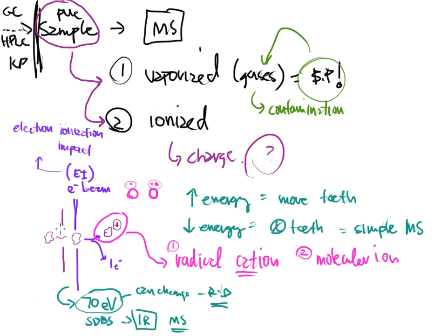So the sample comes into the MS chamber. The sample gets hit with electron ionization energy, and that sample is creating or will create a molecular ion that eventually will become analyzed. This is what the MS is seeing. If the ion does not get created, the MS does not see it. It has to have the positive charge. It's got to, or it will never reach the point of detection.